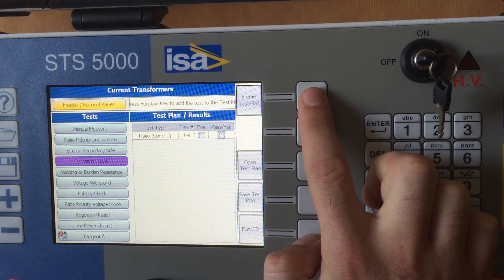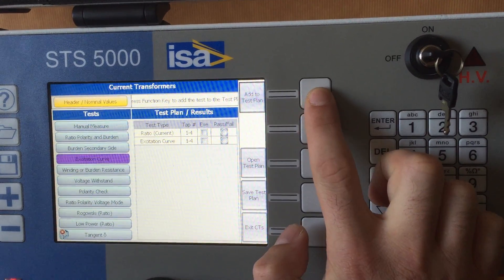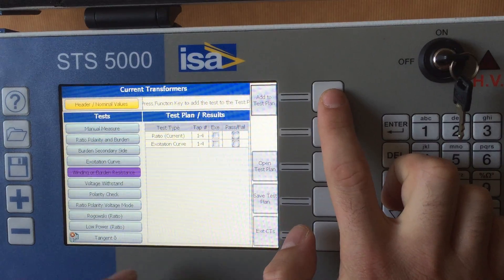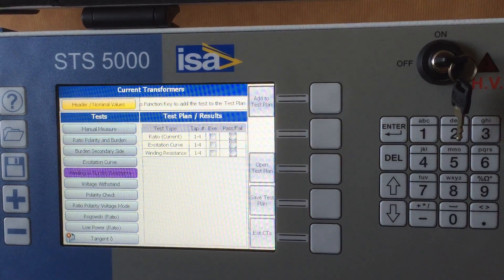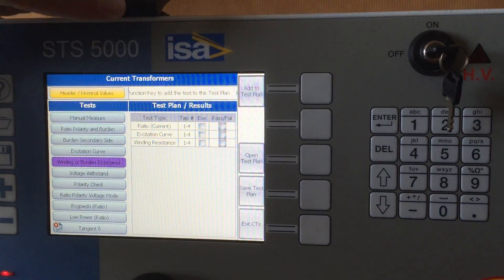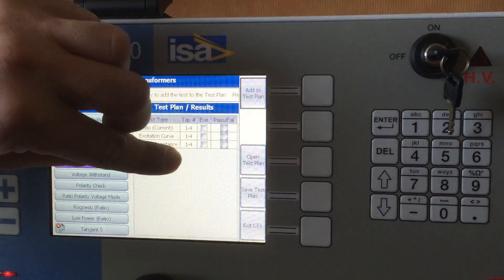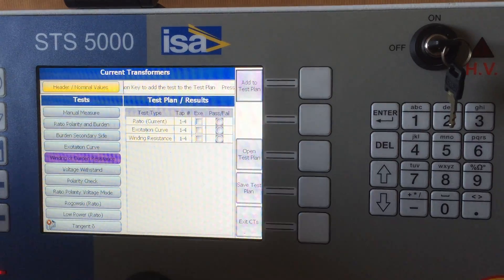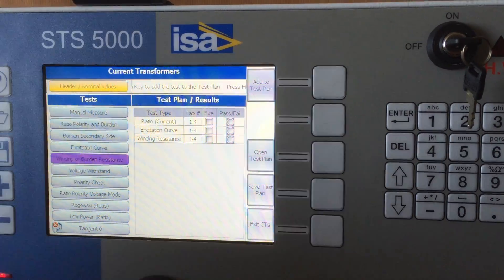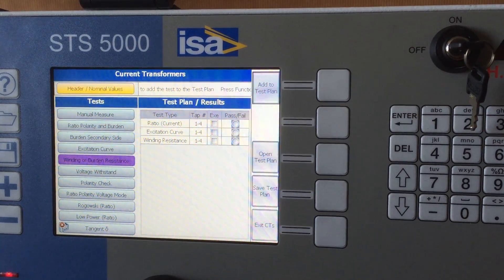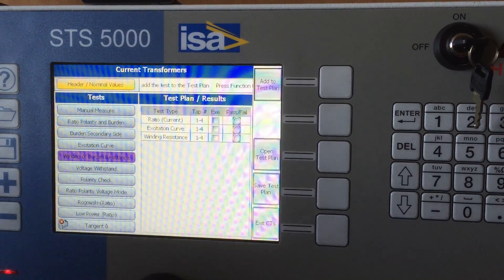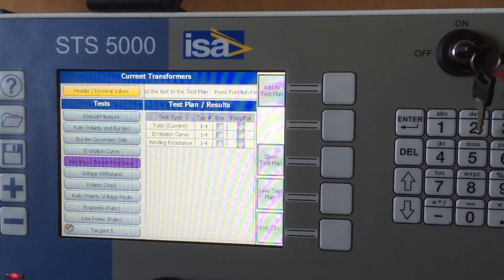Then I will also do an excitation curve and, for example, a winding resistance. Since I defined that my CT has four taps, this is now a ready test plan which will be done step by step, test by test.